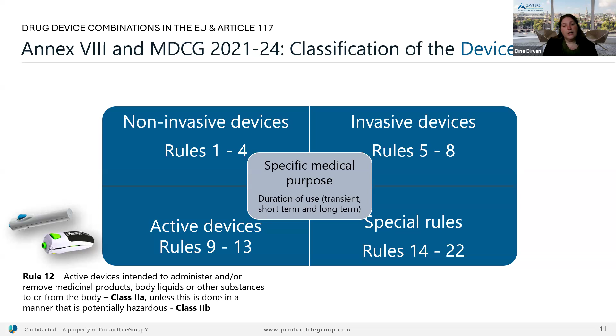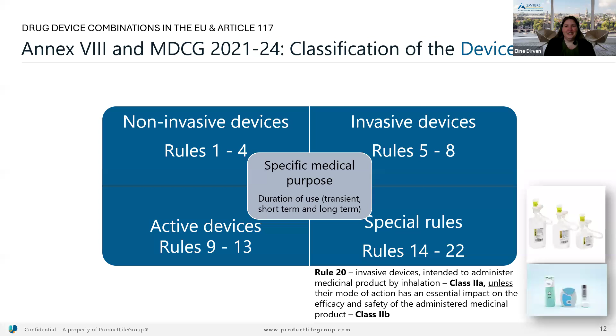If we go to an example of the active devices, then we see that jet injectors would fall under Rule 12. Those are active devices which are intended to administer the medicinal product to the body, and usually they are classified as class 2A. Then when we go to the special rules, we see that inhalers would fall under Rule 20. These are invasive devices intended to administer medicinal product by inhalation, and typically they are classified as class 2A. There is still a condition that it might be a class 2B, as you can see. So what we can conclude from this slide is that quite often a notified body is needed.